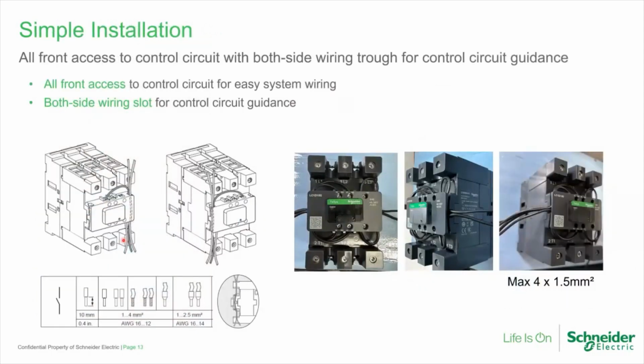We have been talking about simplicity, and when it comes to simplicity, all the control circuit contacts are given on front access. You can see that the power poles are provided on the back, so that while the panel builder is doing wiring, he will first go through the power cabling on the backside, and while he has to do control cabling, he doesn't have to open his power contacts again. Hence all the control circuitry, be it coil connections, NO contact, or NC contact, is on the front.